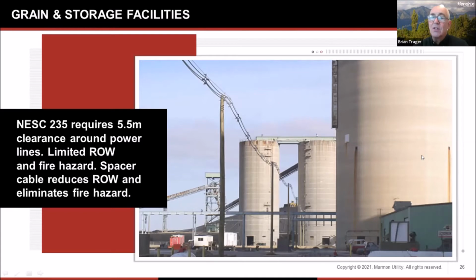So, for grain storage sites, we've got a limited right-of-way, and it's an extreme fire hazard. So these really tiny grain particles are flammable. Spacer cable will reduce that right-of-way and entirely eliminate that fire hazard.